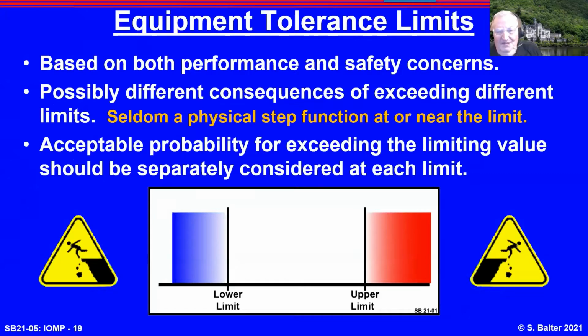Let's look at these limits again. There are, in this example, a lower limit, which is an inconvenience, and an upper limit, which may be a real safety hazard. In general, in the work we do, nothing is falling off a cliff. As you go further beyond the limits, things get more dangerous. So you have to look at each of these values and decide where to put the limits. If you have a manufacturer, I'll show you, you may want to locally adjust your testing limits.